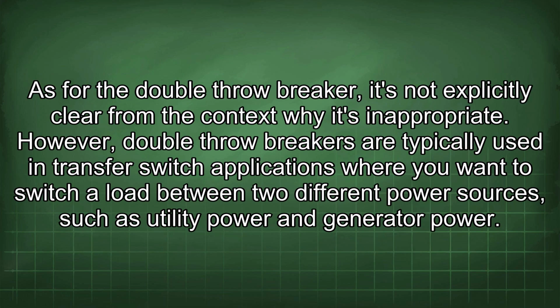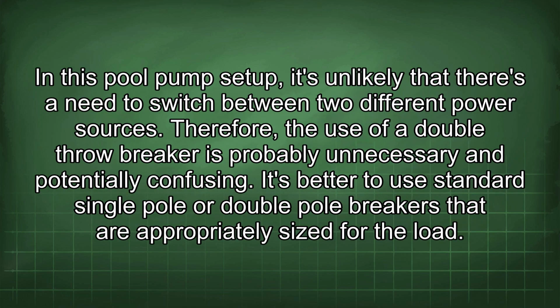As for the double throw breaker, it's not explicitly clear from the context why it's inappropriate. However, double throw breakers are typically used in transfer switch applications where you want to switch a load between two different power sources, such as utility power and generator power. In this pool pump setup, it's unlikely that there's a need to switch between two different power sources. Therefore, the use of a double throw breaker is probably unnecessary and potentially confusing. It's better to use standard single pole or double pole breakers that are appropriately sized for the load.